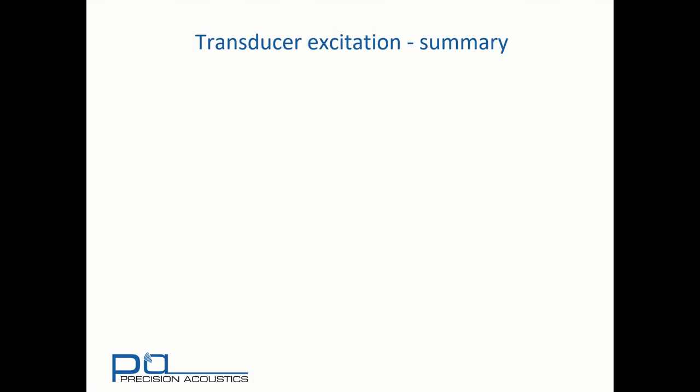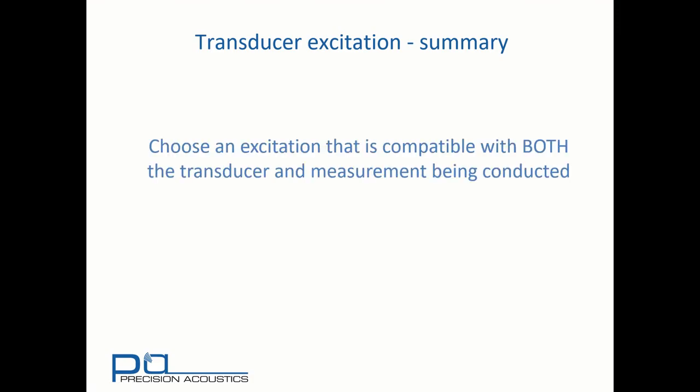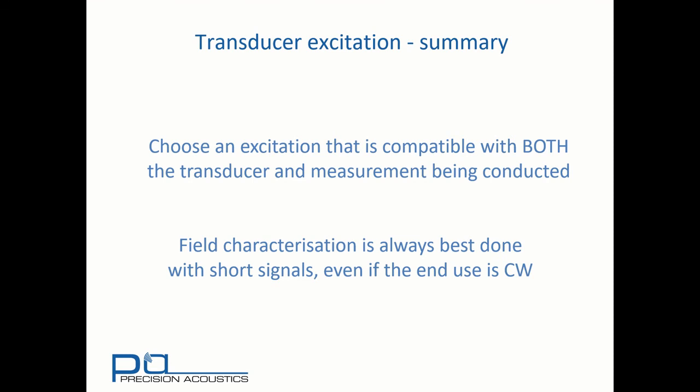So, to summarize, it's important to choose an excitation that is compatible with both the transducer and the measurement being conducted. And field characterization is always best done with short signals, even if the end use is continuous wave.